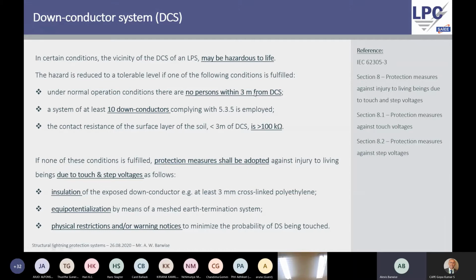A second item says that if we have at least 10 down conductors, 10 different ones, parallel path, remember, from the top to the bottom, we are reducing the hazard to the human being. Again, just preaching that less is not more, more is more. We need to try and have as many down conductors as possible. And remember again, if we have the sheets or the I-beams or the reinforced concrete, we obviously have tens to the hundreds of down conductors going from the roof to the earth.